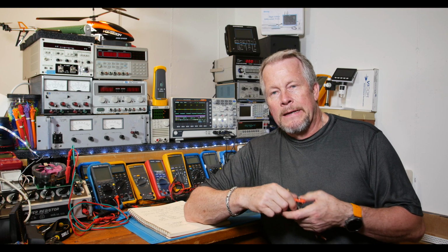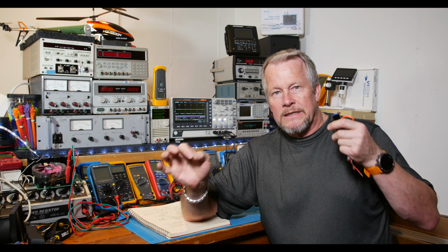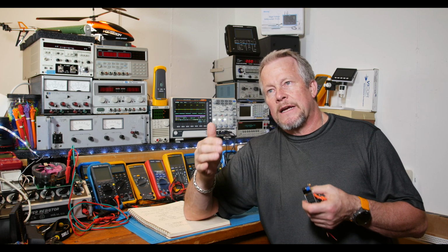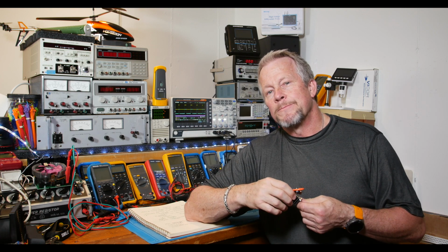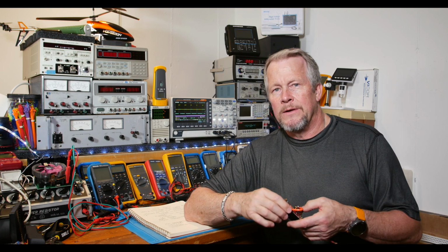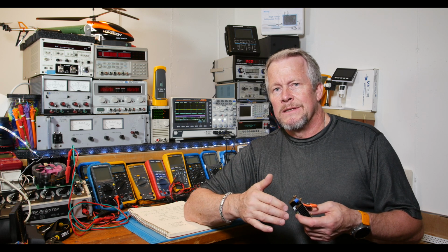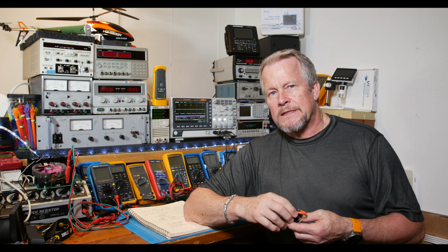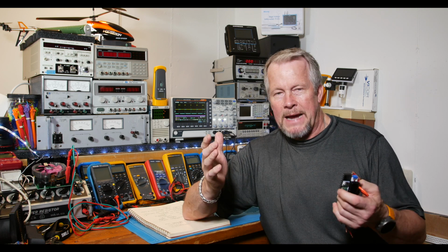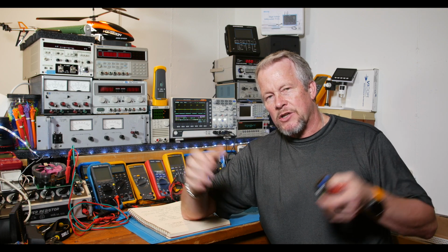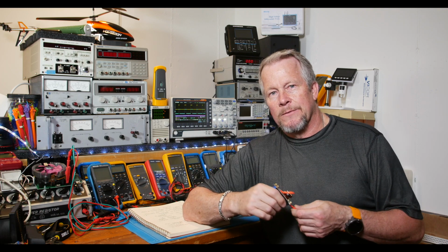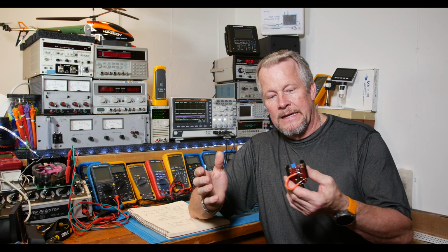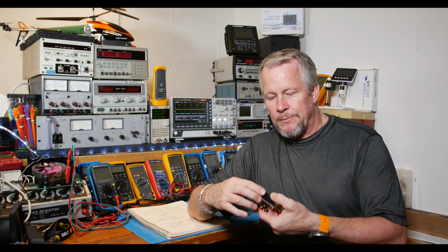You have a lot more diodes. Each diode's conducting or commutating, and there's not this strict on-off cycle you get with the normal bridge rectifier. So multi-phase transformers are a great, robust solution. You don't have a lot of semiconductors and control circuitry to go wrong. It's just passive: drop in a gigantic transformer, and away you go. So there are a lot of different ways to handle things. I just wanted to bring up all the different kinds of power supplies there are.